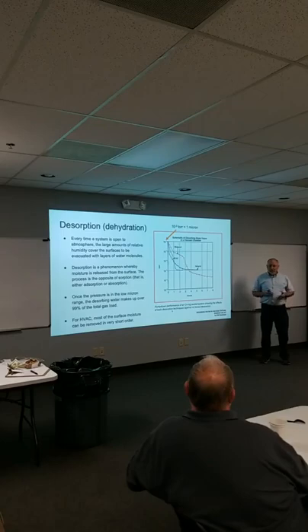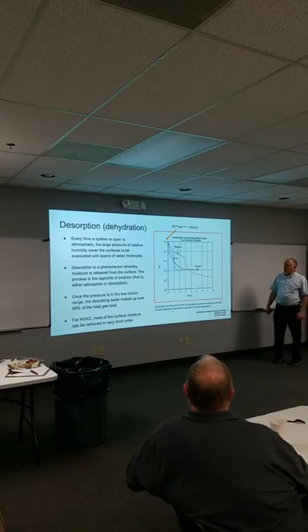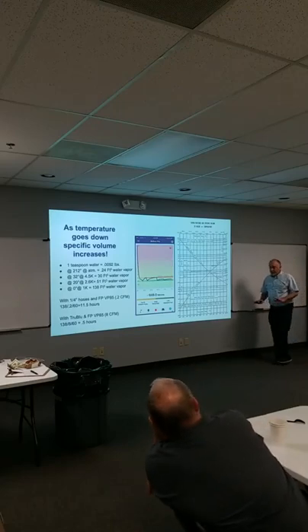All the air is out, all the oxygen's out, all the gases are out. It's 99% water we're pulling out of the system at that point, because water vapor bonds are breaking and we're pulling that moisture out of the system. For an HVAC system, most of the surface moisture can be removed in pretty short order, as long as it's not excessive. So here's what guys don't understand, okay?